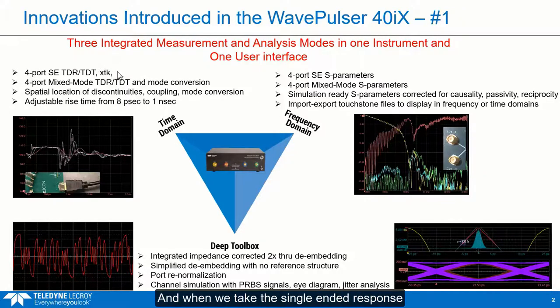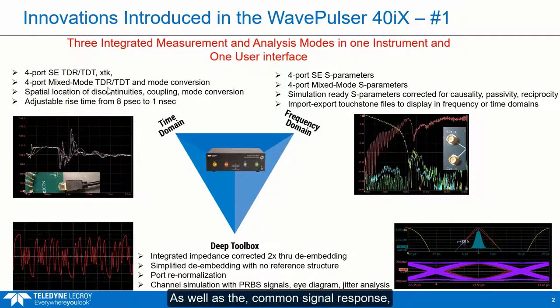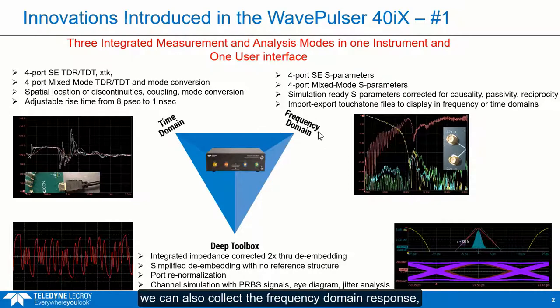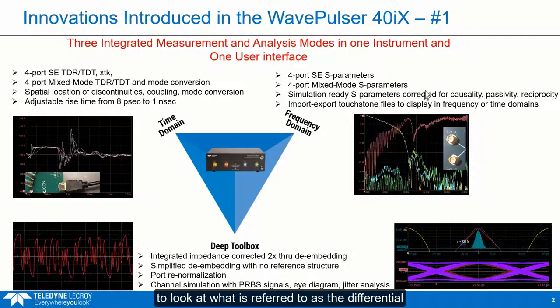When we take the single-ended response and turn it into the mixed-mode response, we can look at the differential TDR response — either the reflected or the transmitted signals — as well as the common signal response and even the mode conversion terms. In addition, in the same instrument, we can also collect the frequency-domain response, which are really the S-parameters. We can get the S-parameters as single-ended S-parameters up to four ports, or we can convert the single-ended S-parameters into the mixed-mode S-parameters to look at what are sometimes referred to as the differential S-parameters.